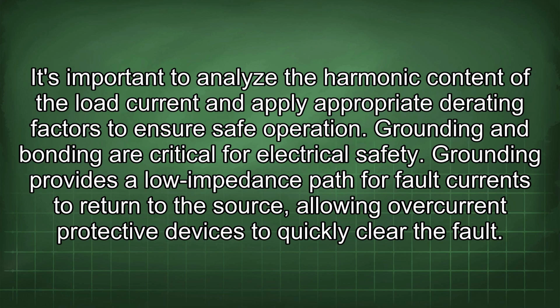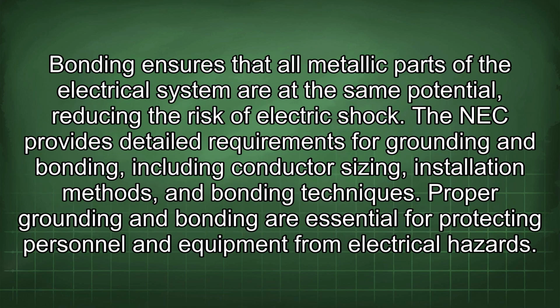Grounding and bonding are critical for electrical safety. Grounding provides a low impedance path for fault currents to return to the source, allowing overcurrent protective devices to quickly clear the fault. Bonding ensures that all metallic parts of the electrical system are at the same potential, reducing the risk of electric shock. The NEC provides detailed requirements for grounding and bonding, including conductor sizing, installation methods, and bonding techniques. Proper grounding and bonding are essential for protecting personnel and equipment from electrical hazards.